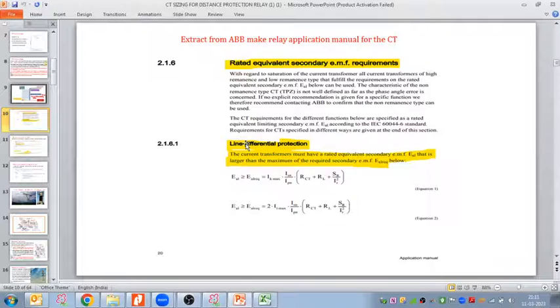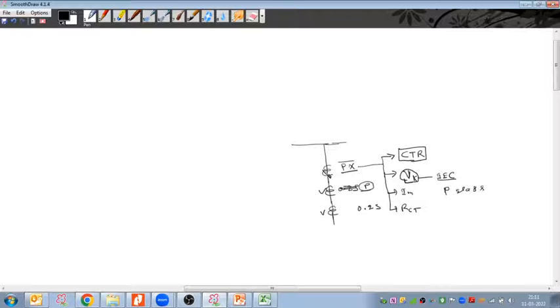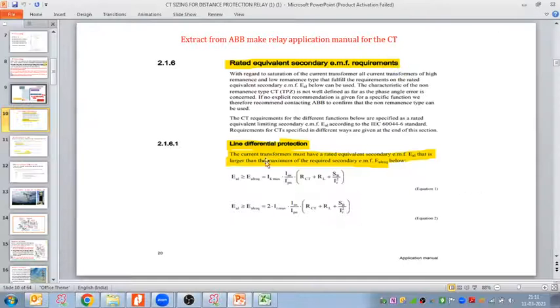I took this extract from the ABB make relay application manual, the same RED670 model for the relay. You can see here the rated equivalent secondary EMF requirement, given in the relay applications manual, page 20. For line differential protection, if we are using this PX class CT, the current transformer must have a rated equivalent secondary EMF, Eal, that is larger than the maximum of the required secondary EMF, Eal required, below.